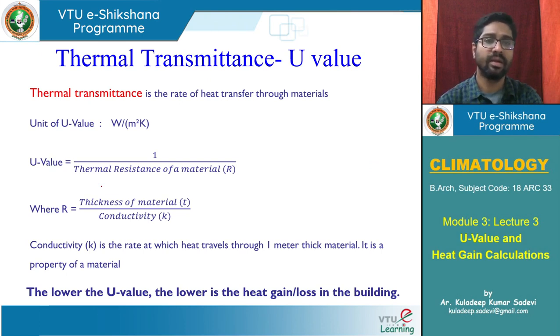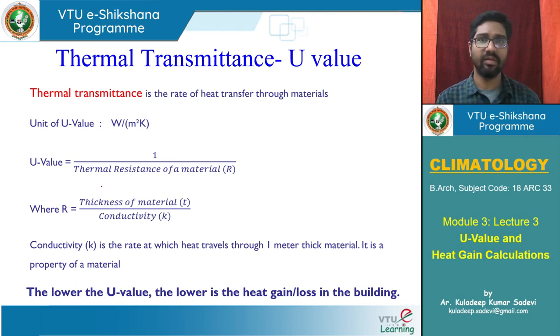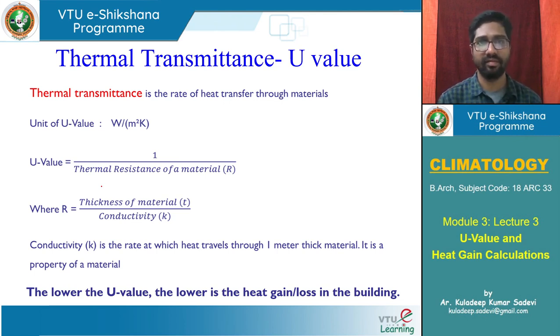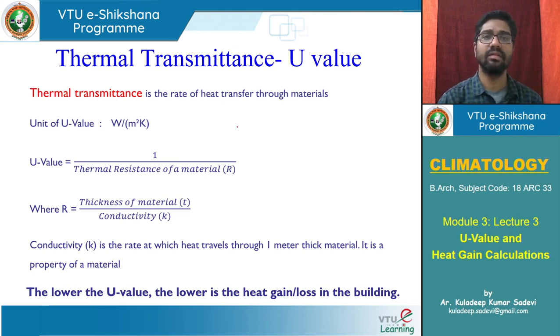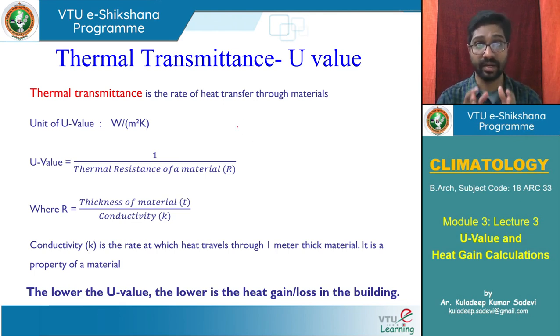Let us understand thermal transmittance, which is U-value. U-value is conductance where we also consider the surface film resistance — both the outer and inner surface film conductance. These two surface film resistances are considered to see the whole unit as one particular component, giving us thermal transmittance, which is U-value.